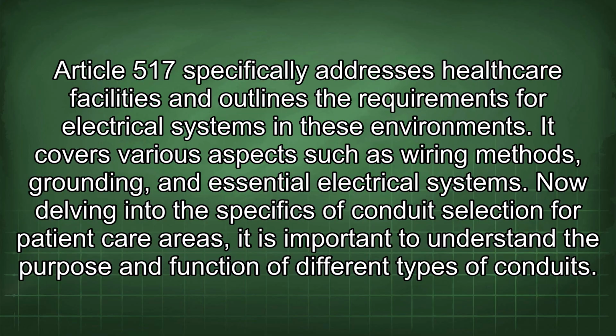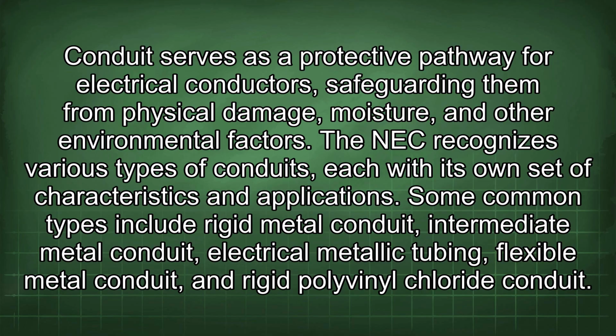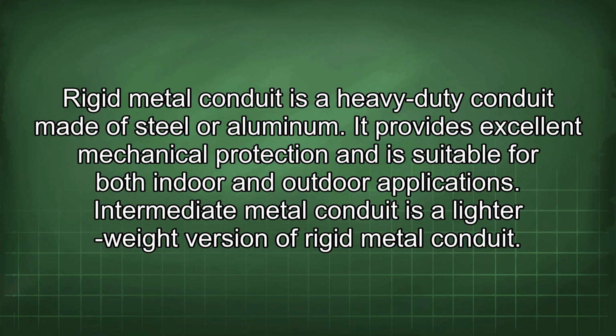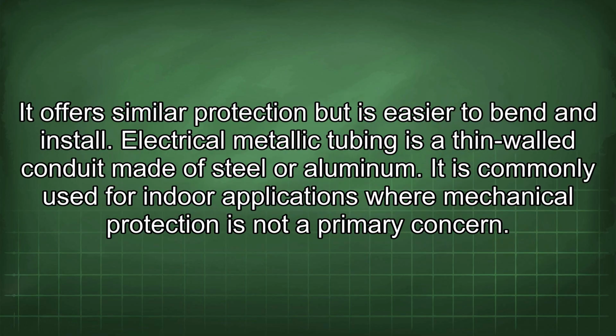Now delving into the specifics of conduit selection for patient care areas, it is important to understand the purpose and function of different types of conduits. Conduit serves as a protective pathway for electrical conductors, safeguarding them from physical damage, moisture, and other environmental factors. The NEC recognizes various types of conduits, each with its own set of characteristics and applications. Some common types include rigid metal conduit, intermediate metal conduit, electrical metallic tubing, flexible metal conduit, and rigid polyvinyl chloride conduit. Rigid metal conduit is a heavy-duty conduit made of steel or aluminum. It provides excellent mechanical protection and is suitable for both indoor and outdoor applications. Intermediate metal conduit is a lighter-weight version of rigid metal conduit. It offers similar protection, but is easier to bend and install.